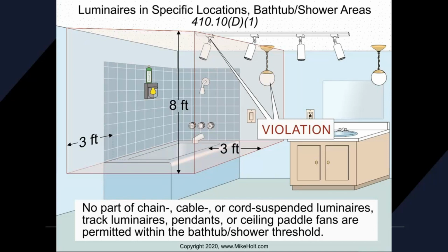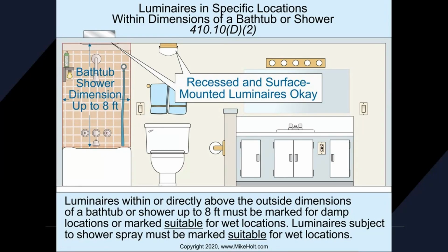But specific to luminaires, 410.10 says no part of a chain, cable, or cord suspended luminaire, track luminaire, pendant, or ceiling paddle fan is permitted within the bathtub shower threshold. Recessed and surface-mounted luminaires are okay in that area, but they must be marked for damp locations or marked suitable for wet locations. Luminaires are subject to shower spray and must be marked suitable for wet locations if they're in the shower, right?